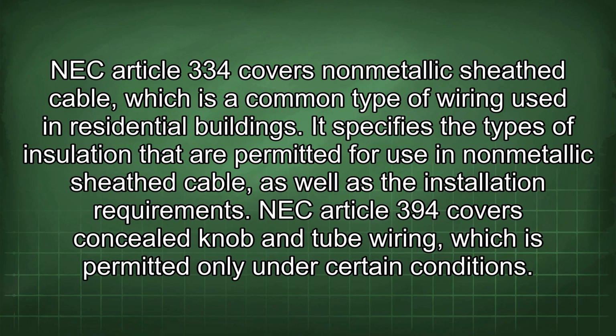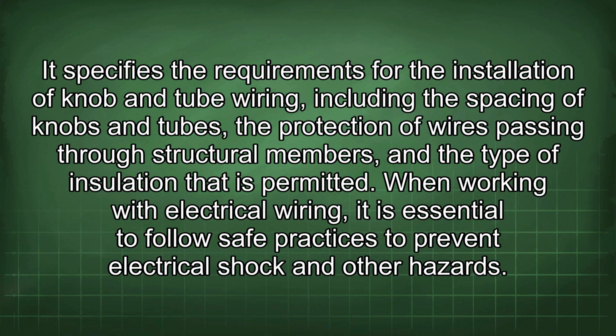NEC Article 334 covers non-metallic sheathed cable, which is a common type of wiring used in residential buildings. It specifies the types of insulation that are permitted for use in non-metallic sheathed cable, as well as the installation requirements. NEC Article 394 covers concealed knob and tube wiring, which is permitted only under certain conditions. It specifies the requirements for the installation of knob and tube wiring, including the spacing of knobs and tubes, the protection of wires passing through structural members, and the type of insulation that is permitted.